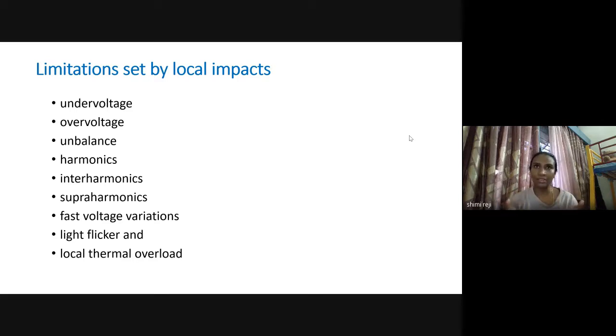Similarly, unbalance is the ratio of negative sequence to positive sequence voltage, and as per the standards the value should not go above 2%. If it goes above 2%, unbalance is created. So this EV-PV combination may also create unbalance. In future, let us think of a street where many houses are going to charge their EVs. And with PV, in many houses in Chandigarh it is compulsory that a house above a certain area has a PV panel. Such combinations can create problems.